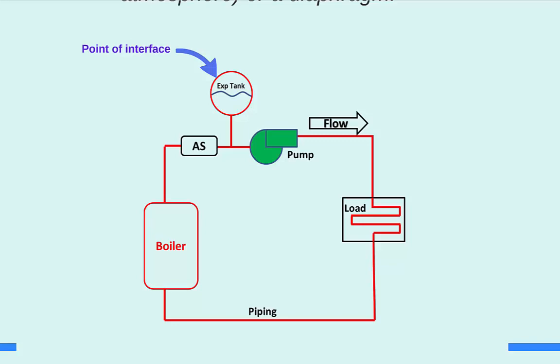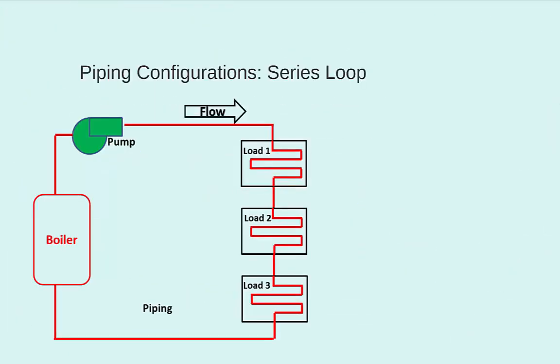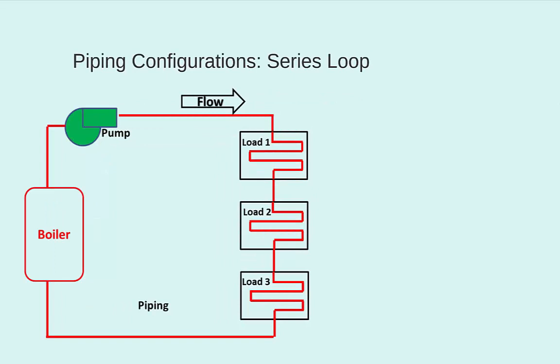Rarely, if ever, do we get to work with hydronic systems as simple as the schematics we have been looking at. There's usually more than one load, or coil, that a given system is serving. And there are different piping configurations that we could use to bring heat to or from all those various coils being served by the hydronic system. The first such piping configuration is that of the series loop.